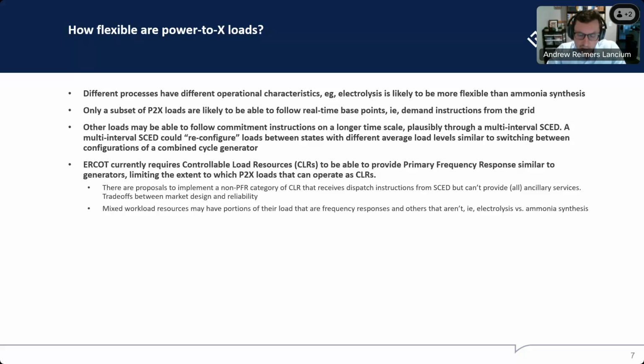Right now, there's a process for being a controllable load in ERCOT where you submit a bid-to-buy curve and get dispatch instructions from the grid. But one of the main bottlenecks is that loads are still required to be able to provide primary frequency response. That means when there's a frequency change on the grid, loads have to be able to drop their load in response to that frequency event, and in proportion to it.